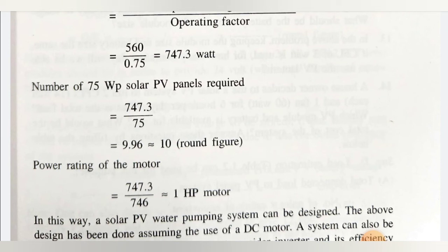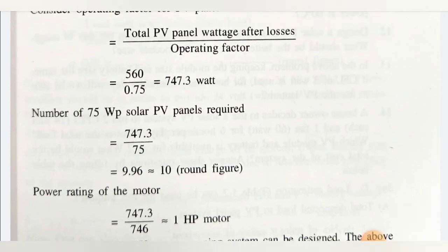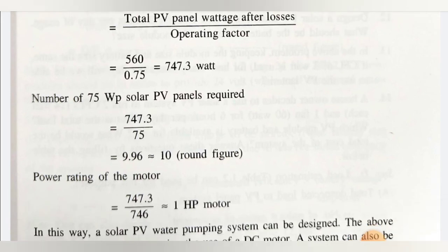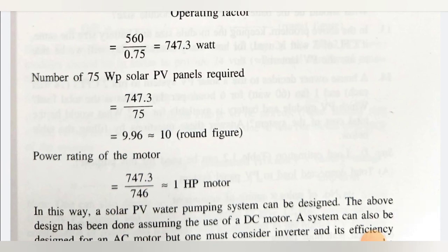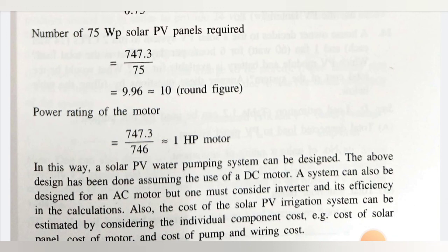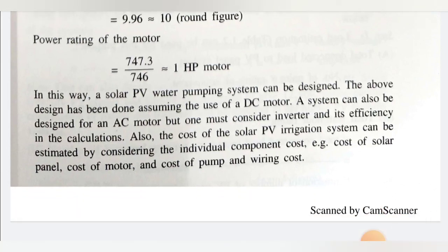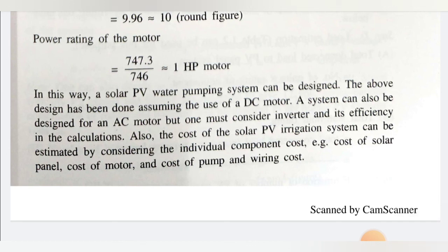Number of 75 Wp solar panels required: 747.3 W ÷ 75 W per panel = 9.96, which rounds up to 10 solar panels. The power rating of the motor required: 747.3 W ÷ 746 W per HP ≈ 1 HP motor. So the designed solar PV water pumping system requires 10 panels of 75 Wp and a 1 HP motor.